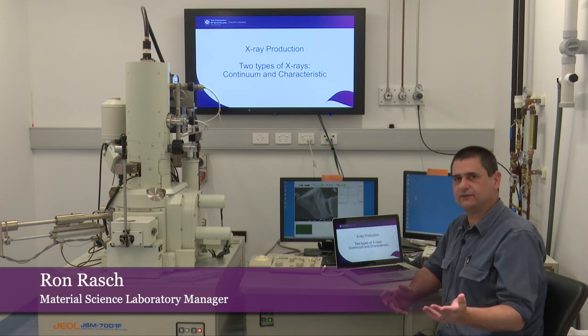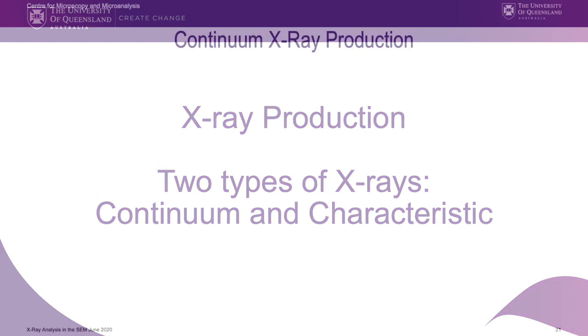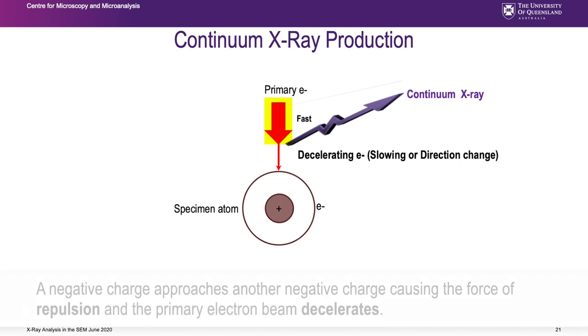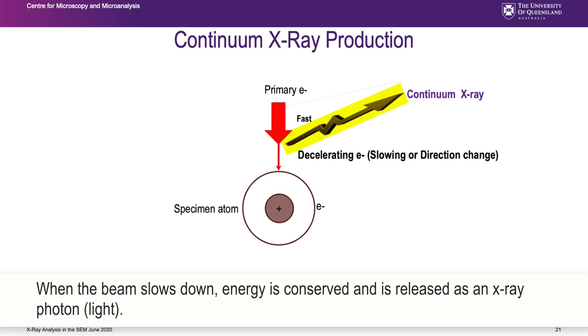Let's talk about X-rays. We have two types: continuum and characteristic. Consider an electron coming down from the SEM column - a typical beam might be 20 kV, so each electron has 20 keV in energy. That electron approaches the atoms of your specimen, which has an electron cloud around it. A negative charge approaching another negative charge causes repulsion, decelerating the primary beam electron. Energy is conserved, so when the beam slows down that energy is released as an X-ray photon - that's called a continuum X-ray.